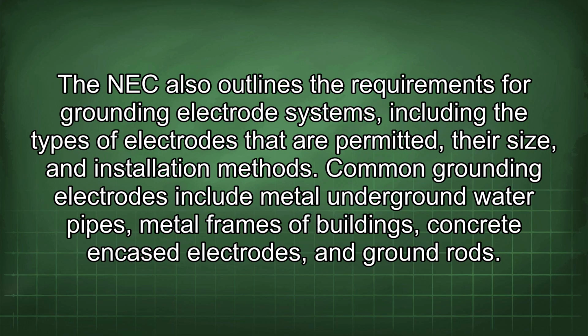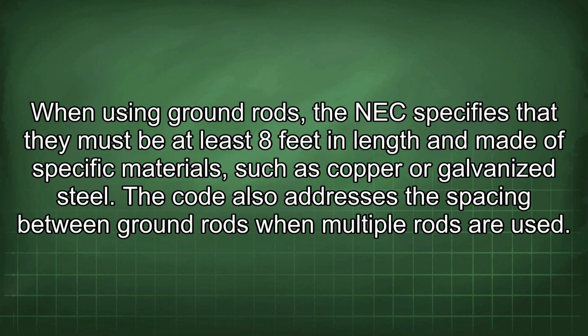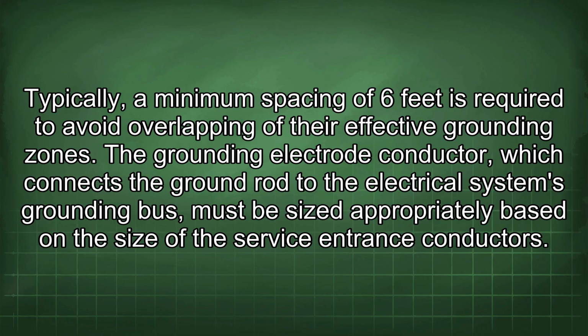The NEC also outlines the requirements for grounding electrode systems, including the types of electrodes that are permitted, their size, and installation methods. Common grounding electrodes include metal underground water pipes, metal frames of buildings, concrete encased electrodes, and ground rods. When using ground rods, the NEC specifies that they must be at least 8 feet in length and made of specific materials, such as copper or galvanized steel. The code also addresses the spacing between ground rods when multiple rods are used. Typically, a minimum spacing of 6 feet is required to avoid overlapping of their effective grounding zones.